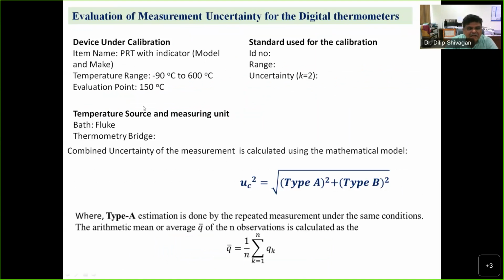So you identify what are the device under calibration requirements: what is the range, resolution and all other parameters. Then you have to choose a standard which is very fine compared to that. The temperature source and measurement unit you have to choose such that the level of uncertainty is easily achievable. The combined uncertainty we always represent as the root sum of squares of type A and type B parameters. Type A is where you directly measure the statistical values, and type B are from the background: the certificate given by somebody, or the stability, uniformity and immersion that you have earlier evaluated. Drift of the standard, or of the DUC, can also be attributed in type B. All these constitute the combined uncertainty.